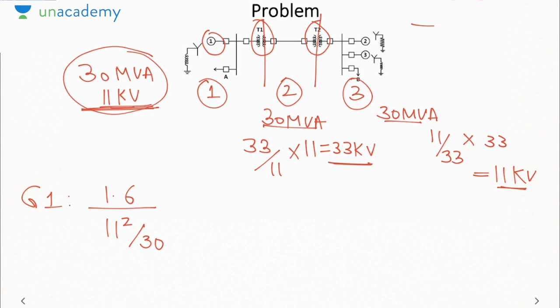The G1 impedance is given to be 1.6 ohm, and G1 lies in section 1 where the base is 30 MVA, 11 kV. So 1.6 divided by the base impedance. Now base impedance is V base square by S base, which is 11 square by 30. So it will come out to be 0.3967 pu. Okay. So whatever base you choose will depend on which section the device is lying in.